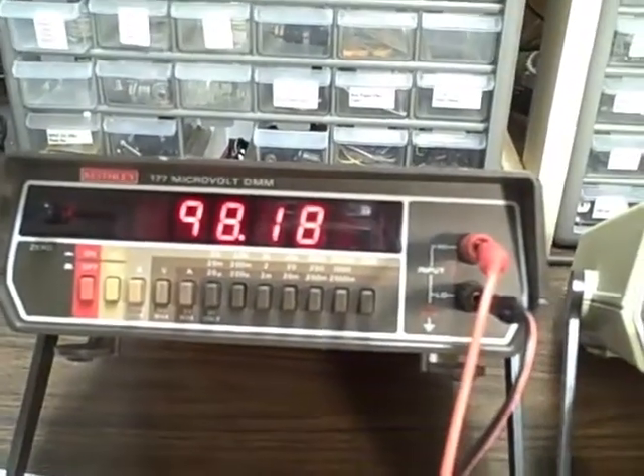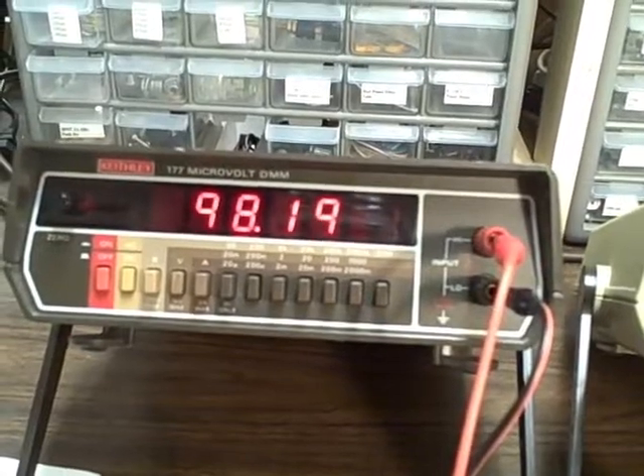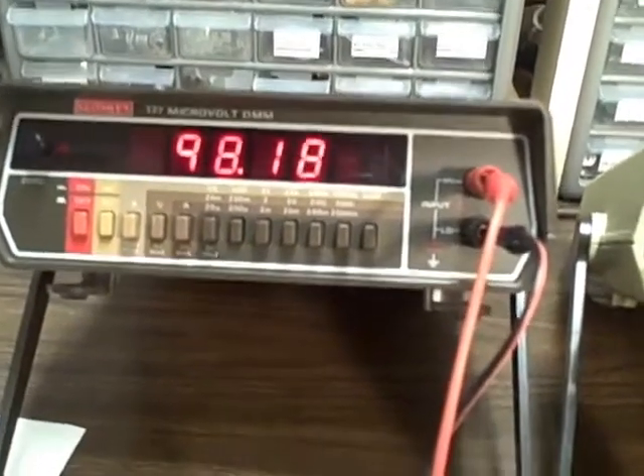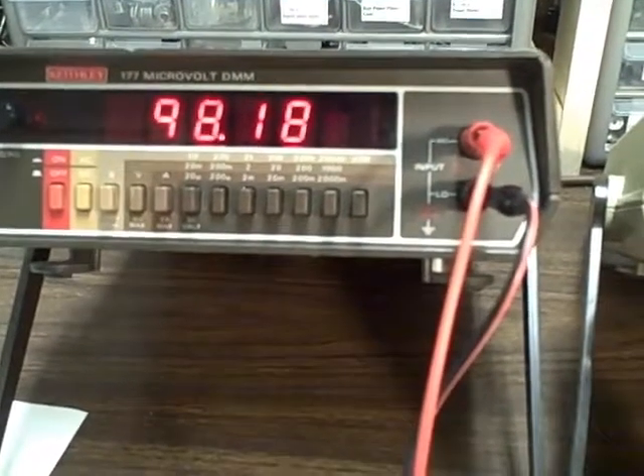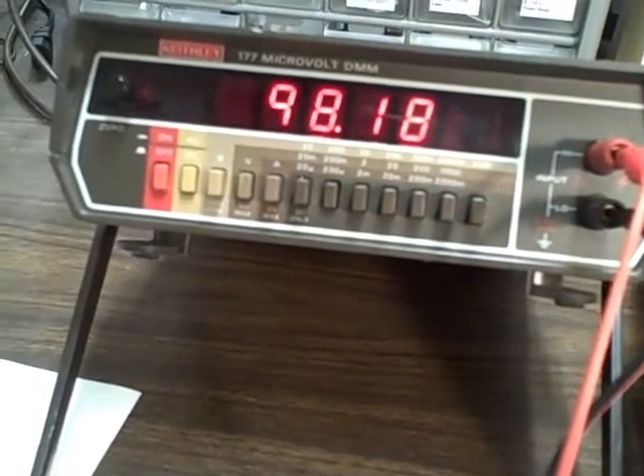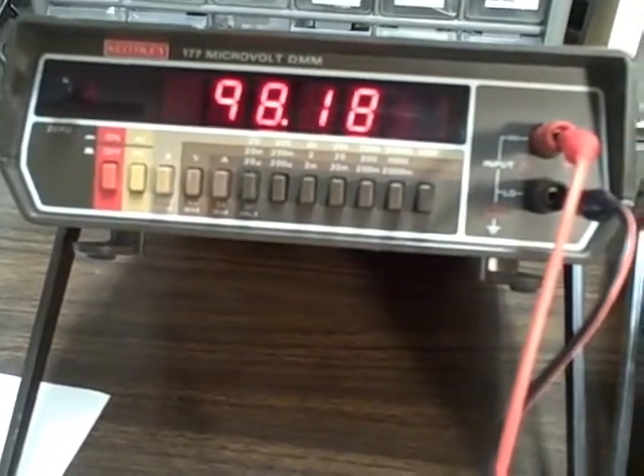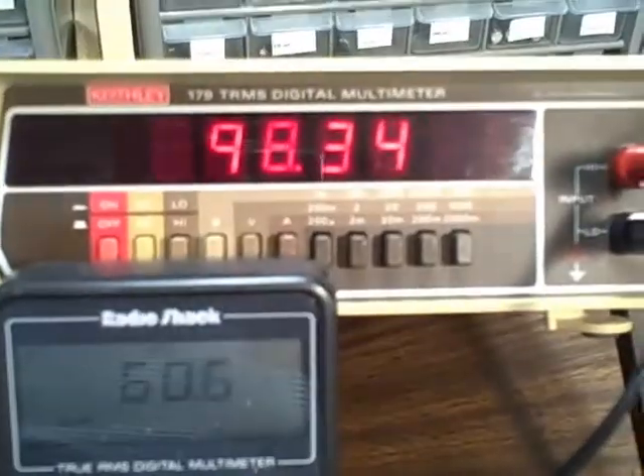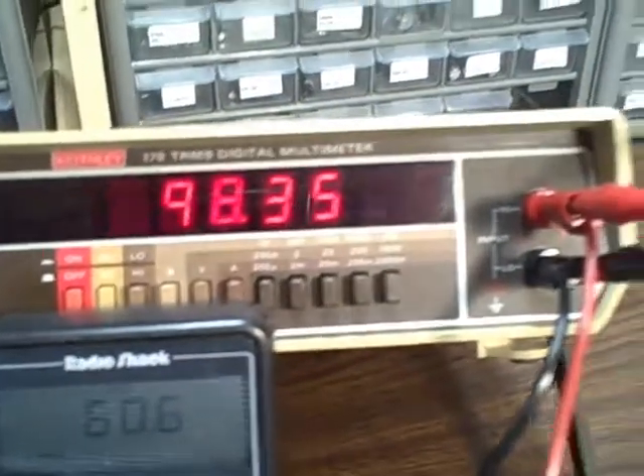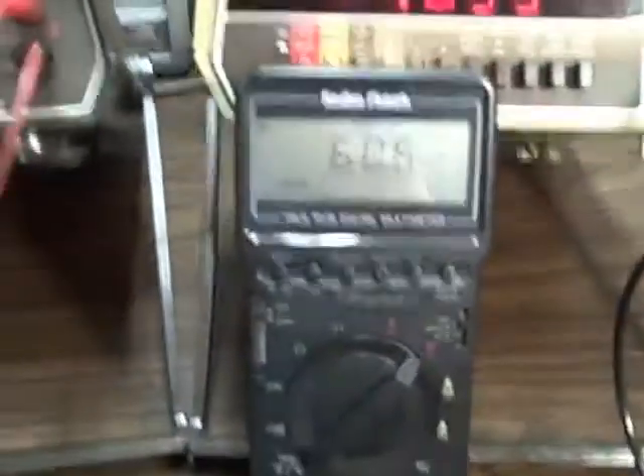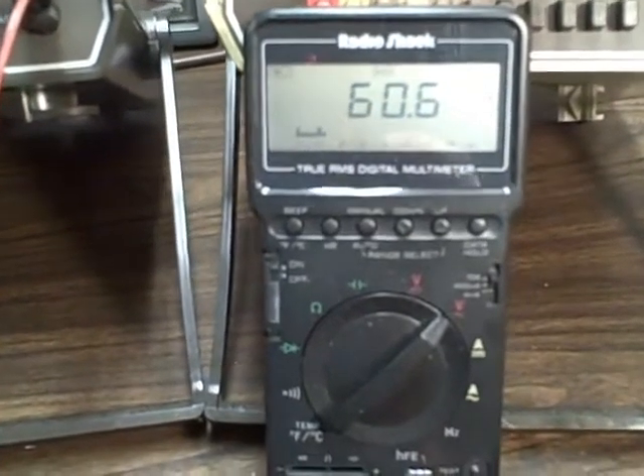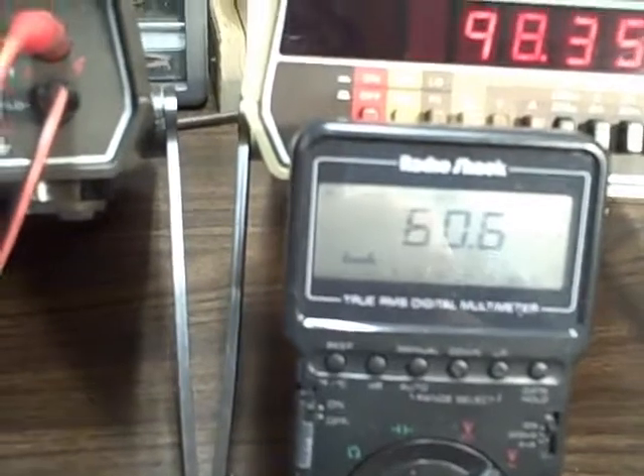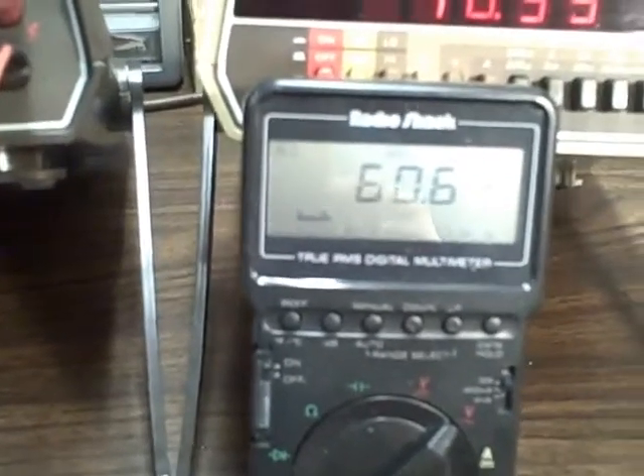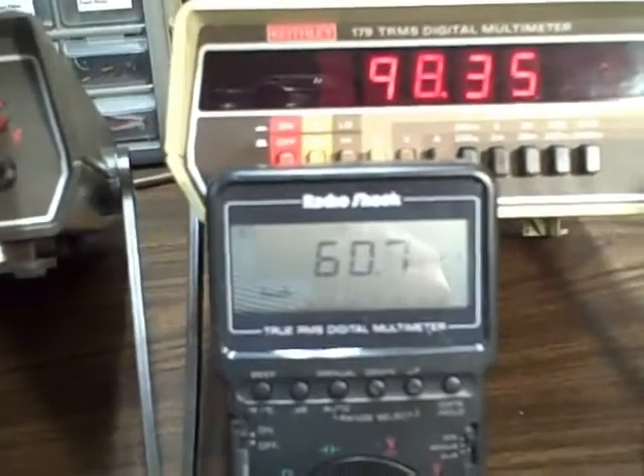All right, we are reading at the 10 kilohertz frequency. I'm reading 98.18 on the 177. I'm reading 98.35 on the 179. And my Radio Shack has suddenly dipped to 60 millivolts. So it doesn't like the low millivolt range at this frequency.